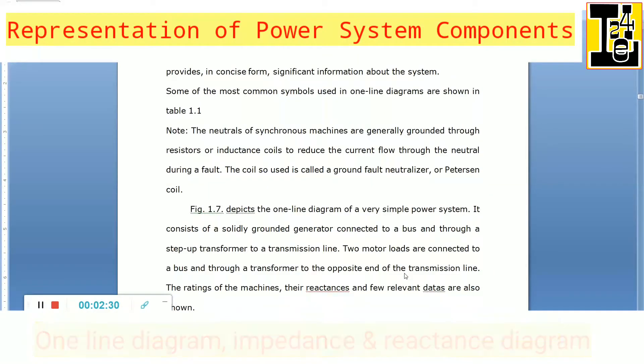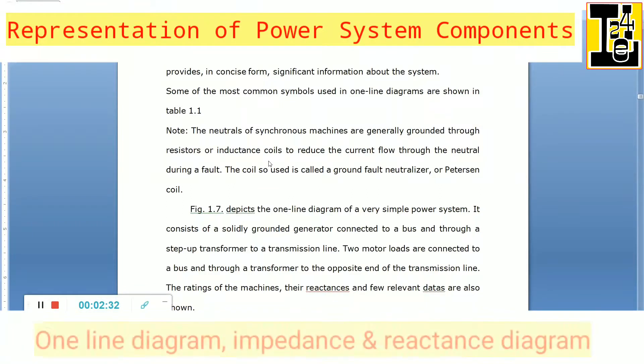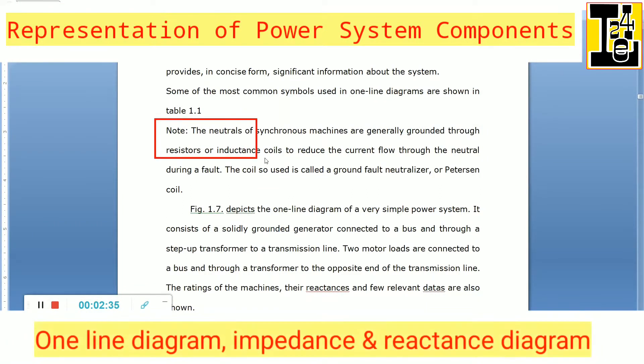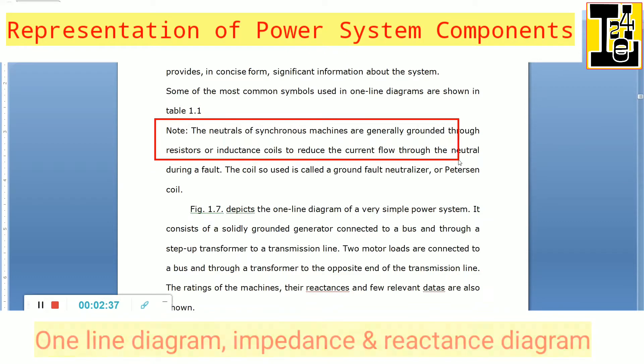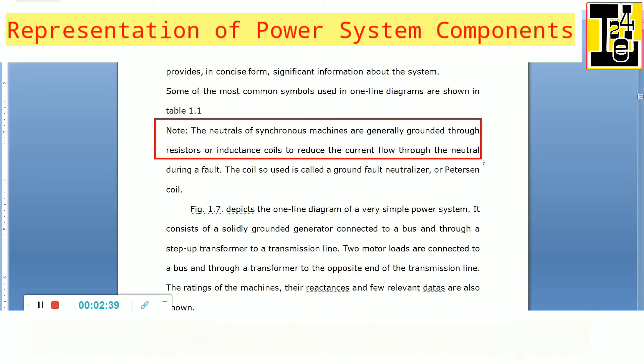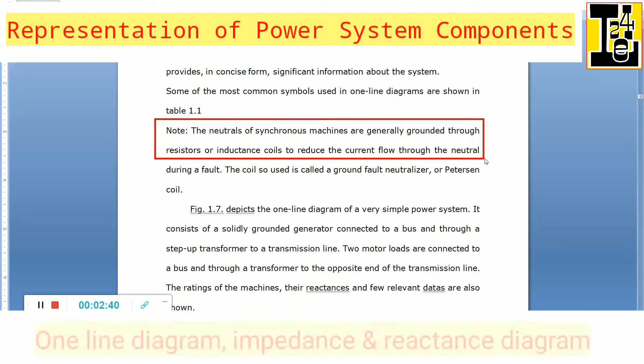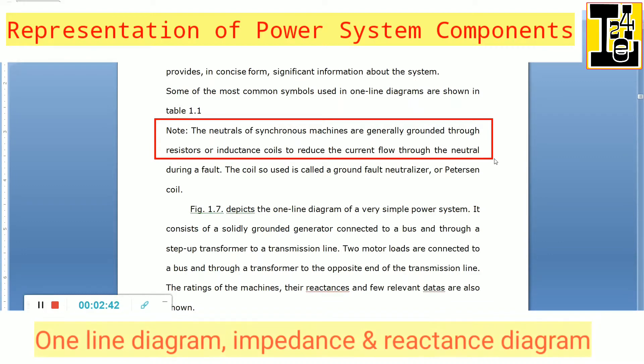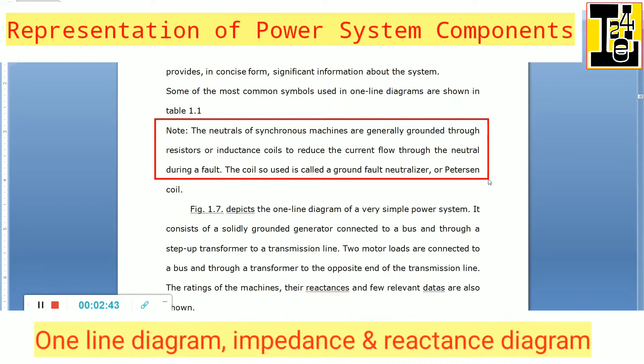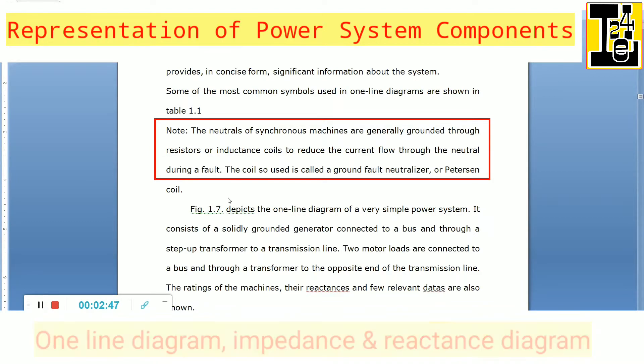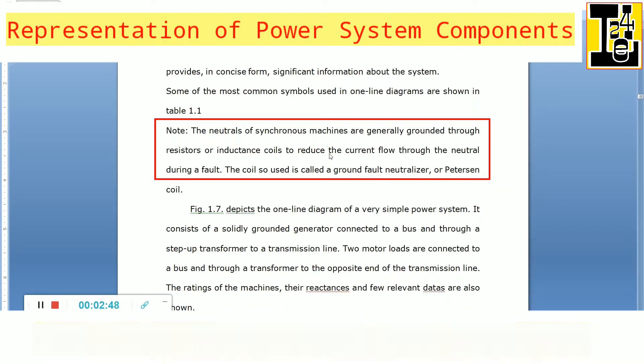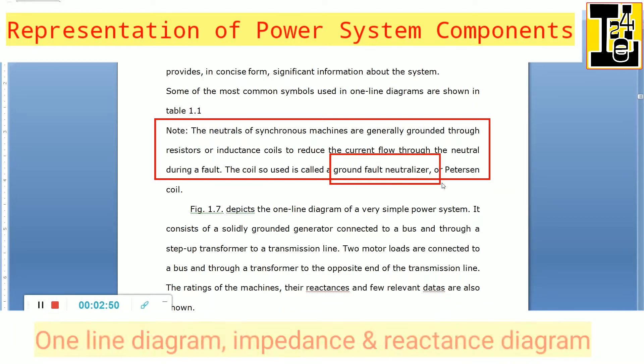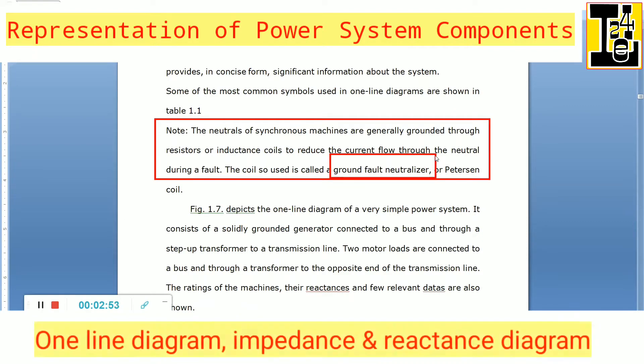The neutrals of synchronous machines are generally grounded via resistors or inductance coils to reduce the current flow through the neutral during a fault. The coil used is called a ground fault neutralizer, also called a Petersen coil.